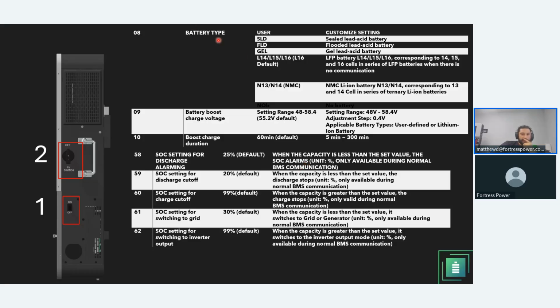So going to the battery settings, by default, L14, L15, and L16 will be the default, and it's going to resort based on what type of cell battery you have. If you have a 15-cell battery like the eForce, I see my guy Maverick Brown there, I know he has one eForce, using the solo inverter, that will resort into L15. If you're using the eBoost, then that will resort into L16. But if you have no battery, then you can select no battery, which is NOB. I apologize that it's not visible, but there is a NOB section.